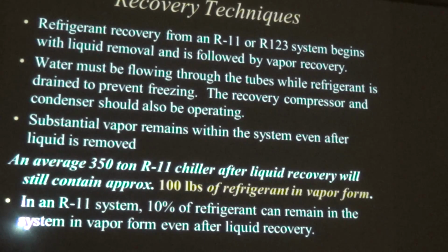Now this one I had to look up the first time I encountered it because I didn't have this presentation. This is a question you see on the back. An average 350-ton R11 chiller, R11, it's a low pressure chiller, low pressure refrigerant, after liquid recovery will still contain approximately 100 pounds of refrigerant in vapor form. So they're saying after you recover the liquid refrigerant from a 350-ton R11 chiller, there's still 100 pounds of refrigerant in vapor form there.